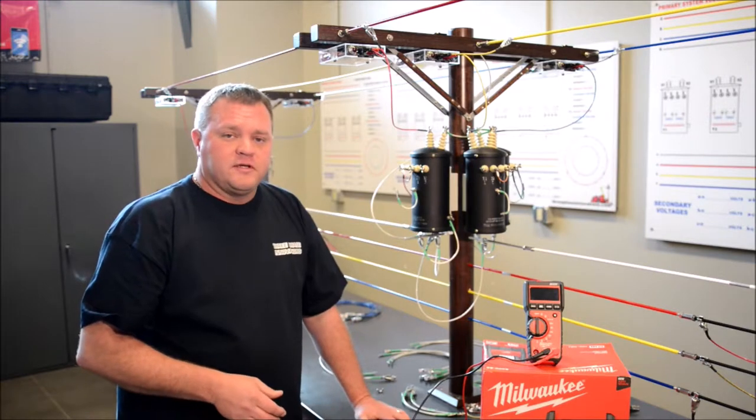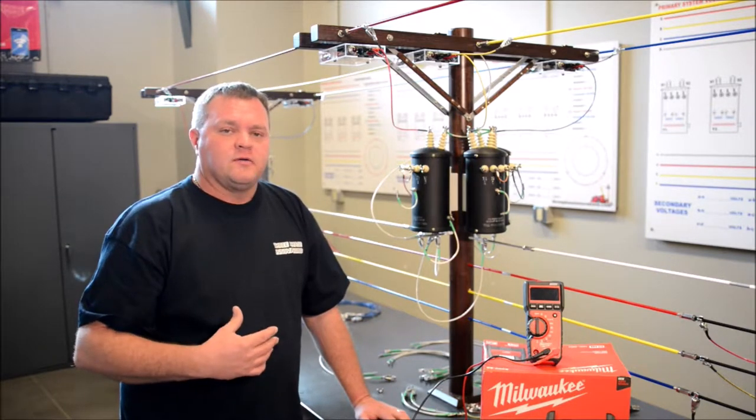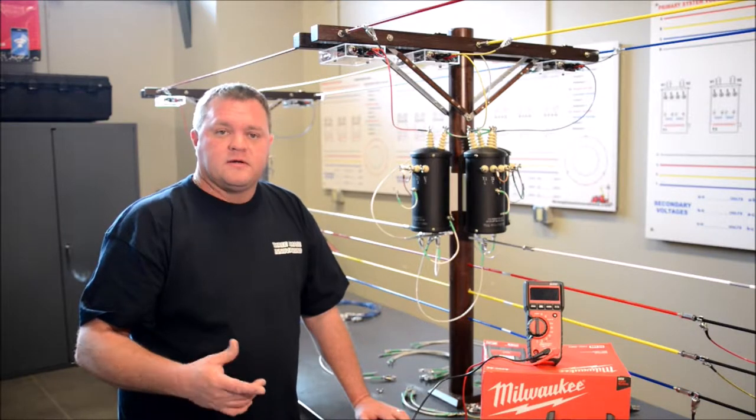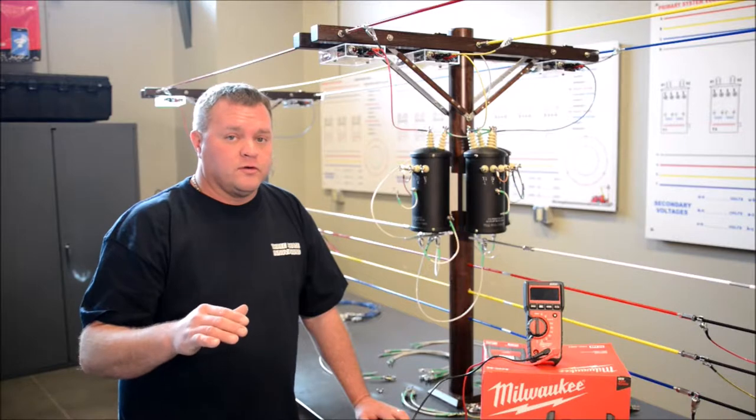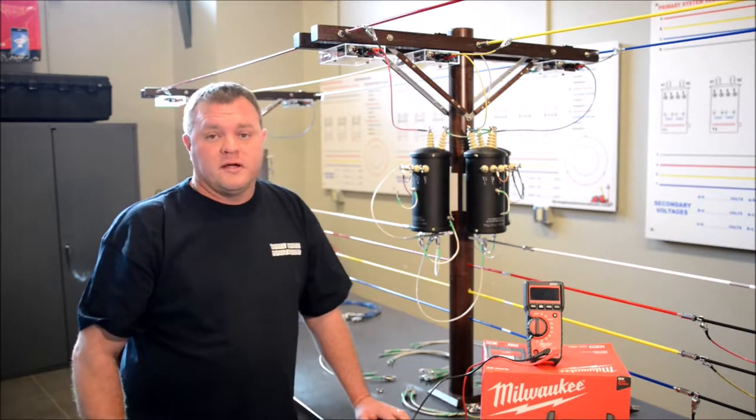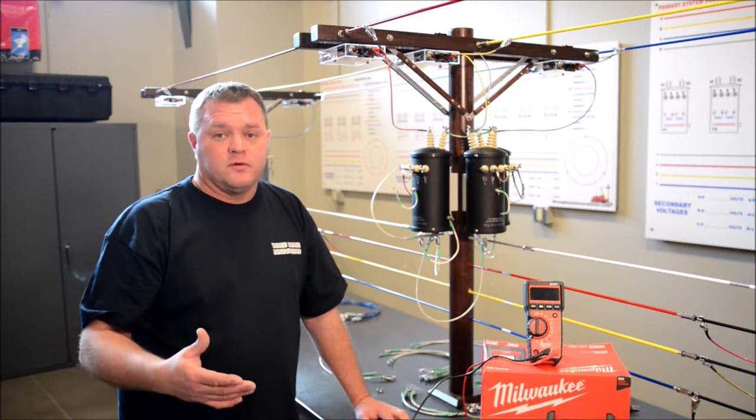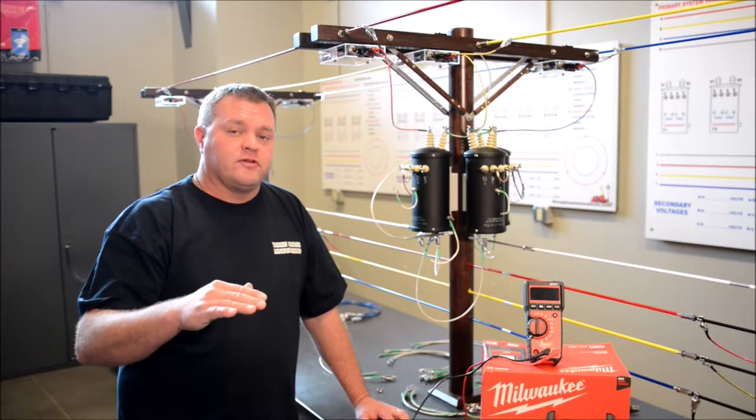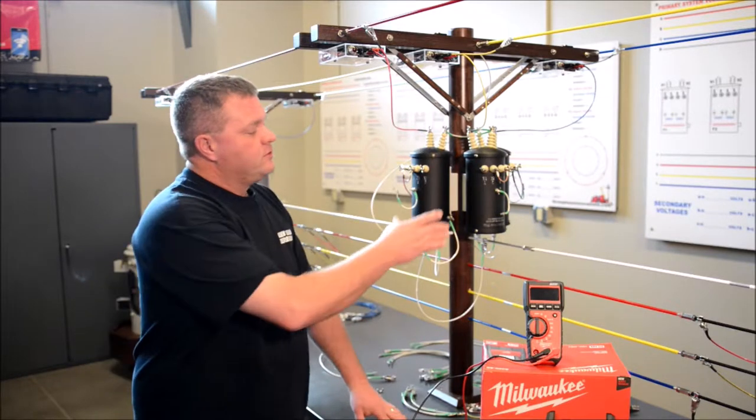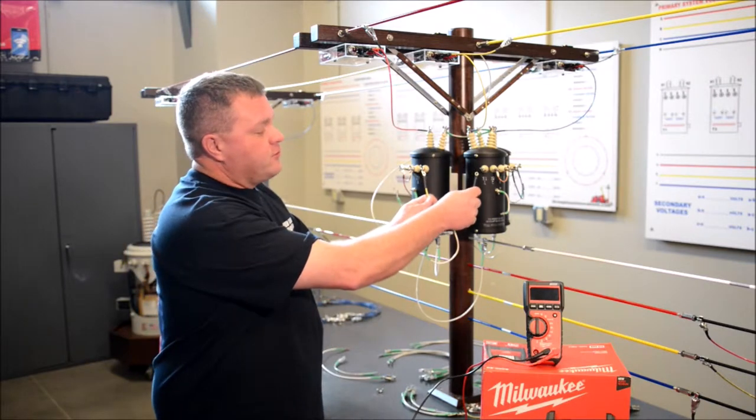The reason being is we've had a few situations where the lineman wired the bank and they checked the polarity on the nameplate and they were all good. The actual wiring of the bank was correct. When they energized the transformer bank, the bank blew up causing some injuries. So from that point on it was a standard test procedure to test right here before we actually close the circuit.